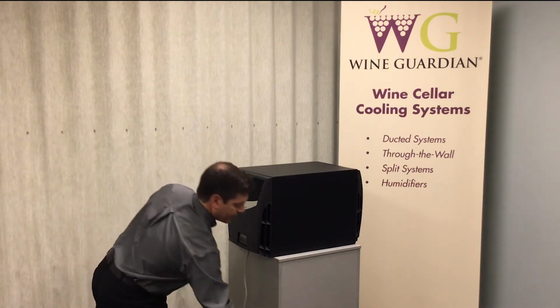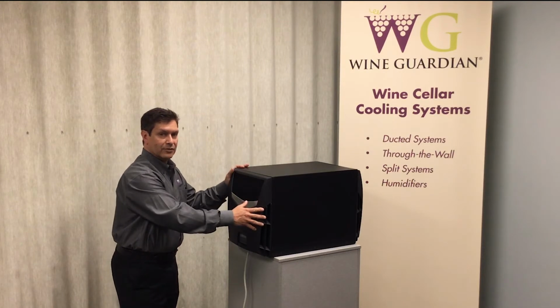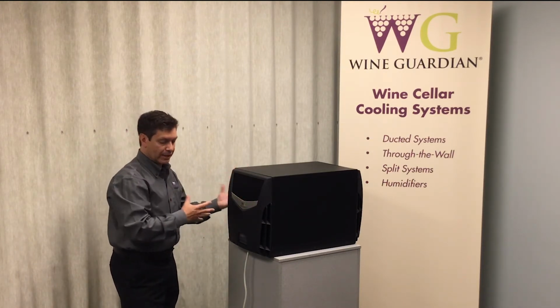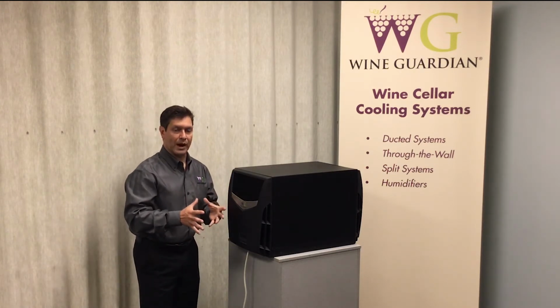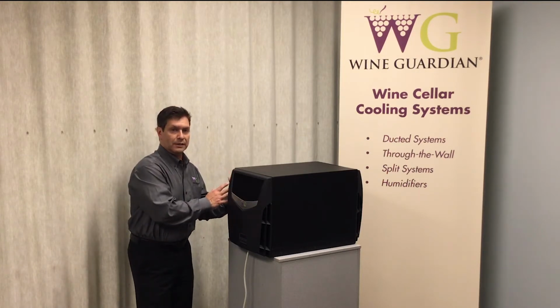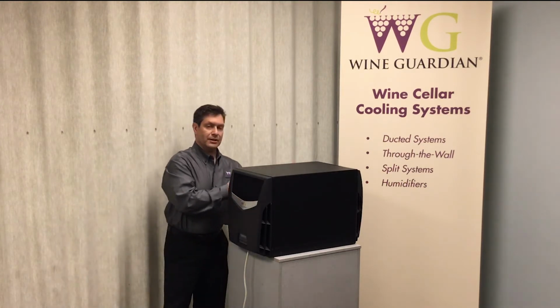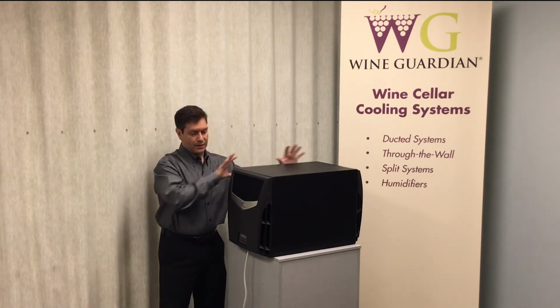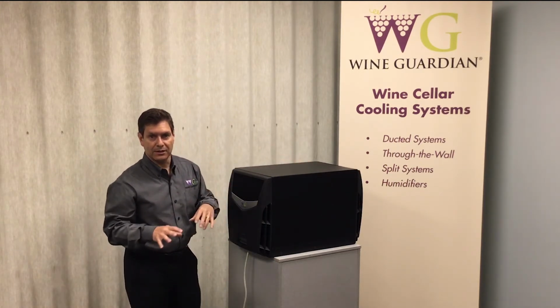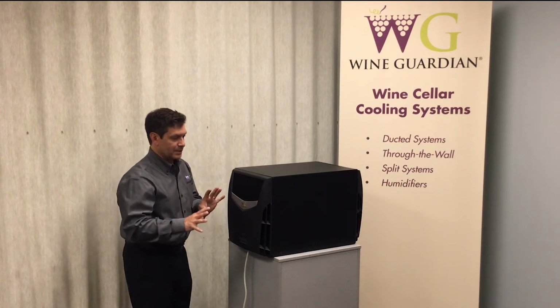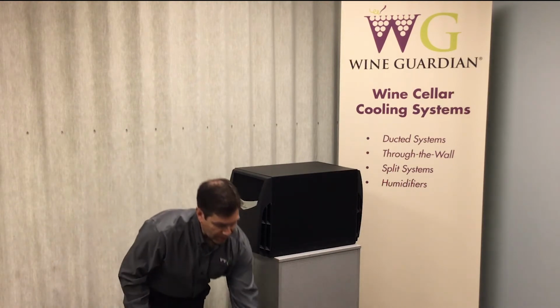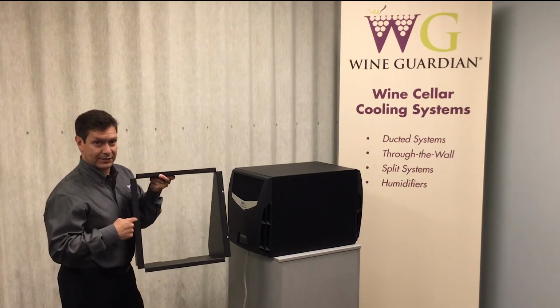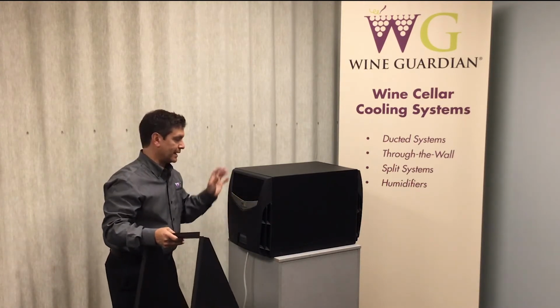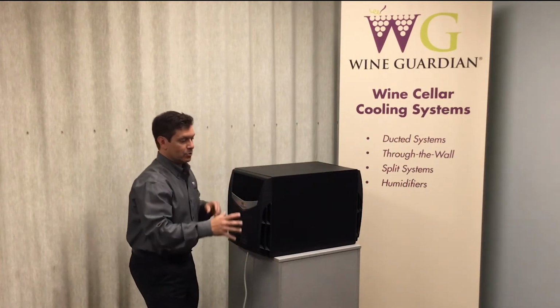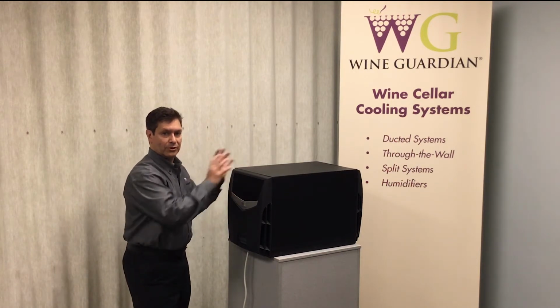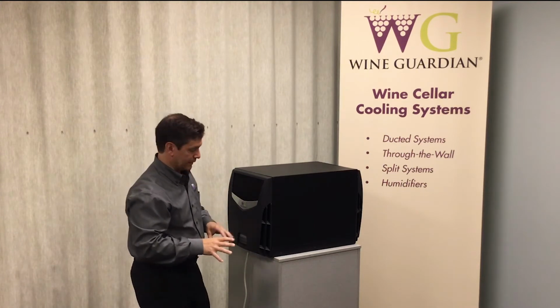Once this is done, the unit essentially slides through that sleeve to any desired length that you'd like, whether you want it flush with the racking in your wine room or maybe flush with the wall in your wine cellar, or you could have it flush on the condenser side. So you can essentially move this unit all along its length on the sleeve until it meets your requirements for mounting. Once the system is set where you'd like it, we require that you caulk the joint between the sleeve itself and the unit, so that we create an airtight package, an airtight system basically between the sleeve and your outdoor or your other room environment. We want to make sure that that wine room is sealed up completely.